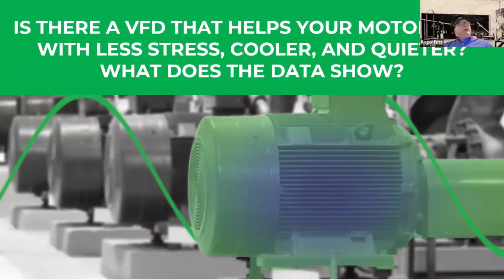So, if we have a drive that is calmer and cooler, because we're providing pure sine waves, we don't get all of those disadvantages. We don't need the grounding ring. We don't need the special insulation in the wire. We can use standard. I mean, we put it on motors that are like 30 years old, and have had zero problems with them.